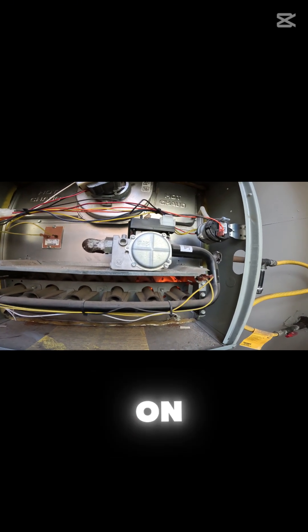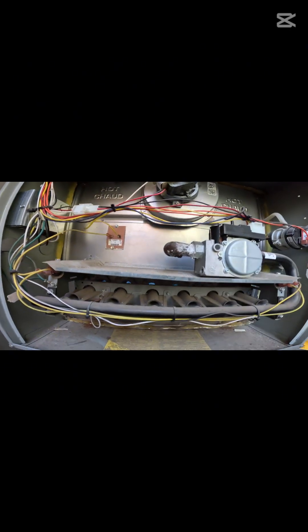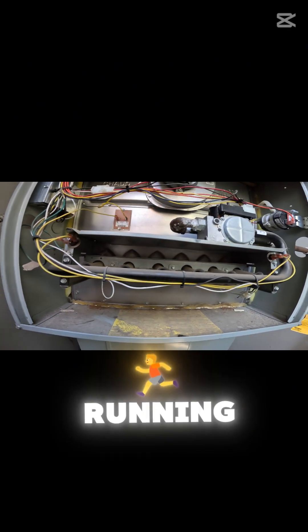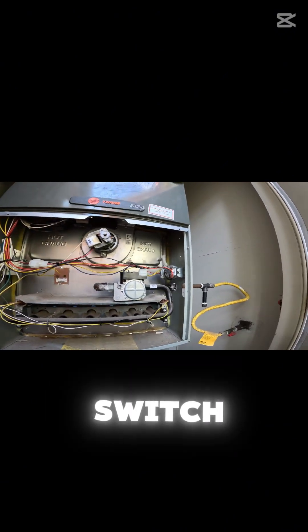Once the gas valve clicks on, it'll ignite. Once it ignites, it sends microamps back to the board, telling the system to keep running. That's how you fix it when the pressure switch isn't kicking in.